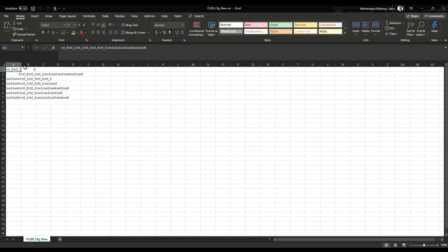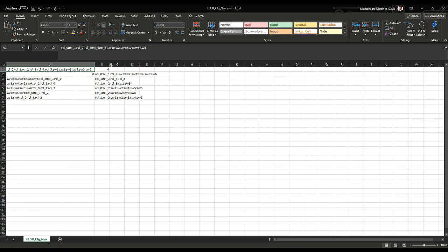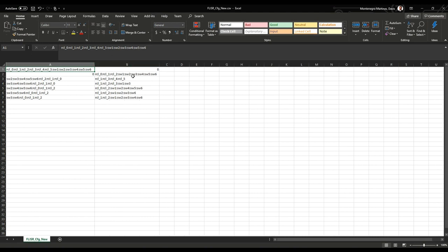The file looks like this. It's just a CSV file in which we define the after fault state and the future topology that we need to adopt. The only switches or circuit breakers that we mention to define a topology are the ones that will be enabled. If the other ones are not in that list, it's because they're open.